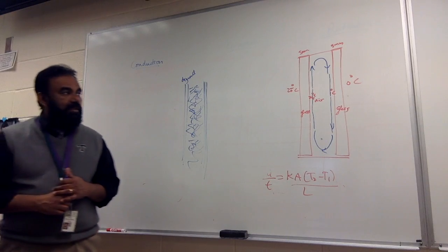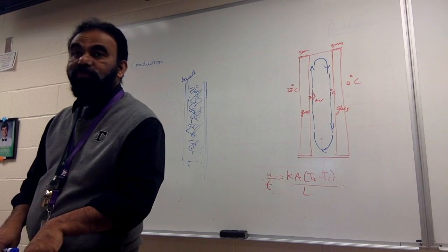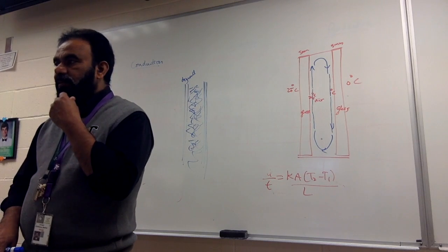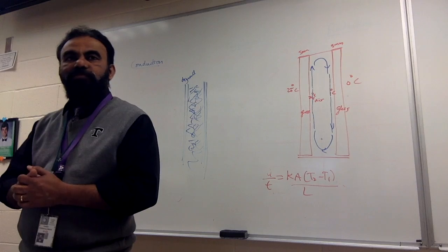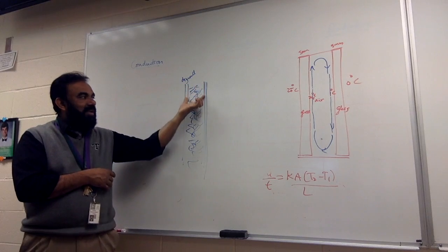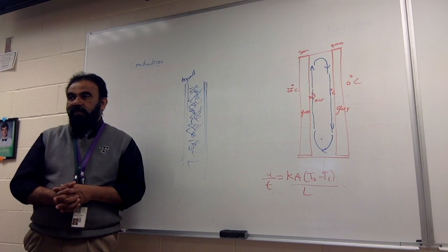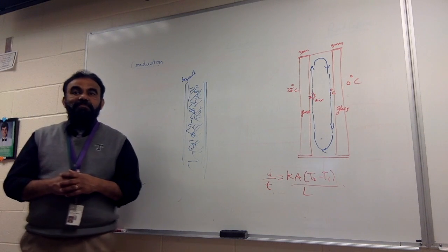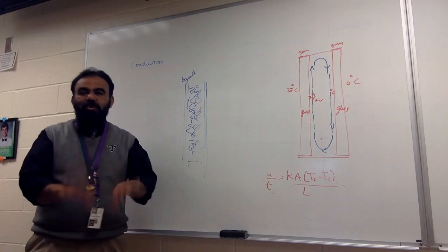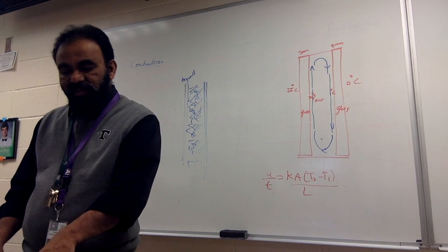You don't want flow. Now, foam kind of insulation is also being used these days, which is polyurethane, which is 0.024. That's better than fiberglass. Have you seen that kind of insulation? Yeah, like it's just expanding foam. All you do is make a hole in this and just push it inside. It'll just fill up this entire place like a wall of polyurethane. And that will be better than fiberglass. The reason is that it is almost air. Because you see, polyurethane is 0.024, air is 0.023.